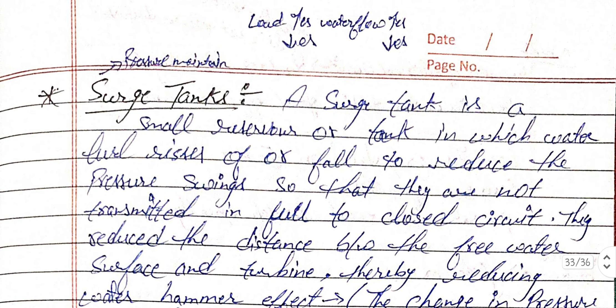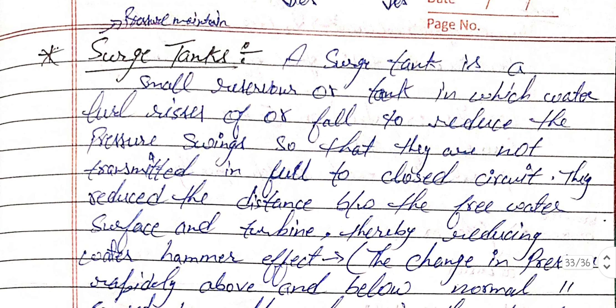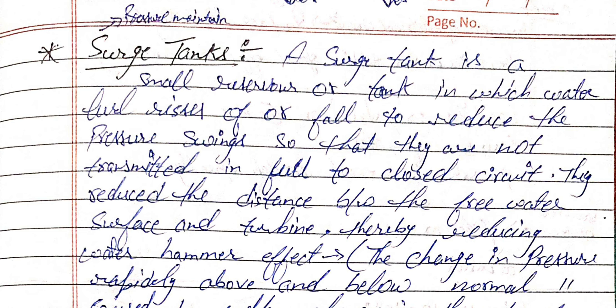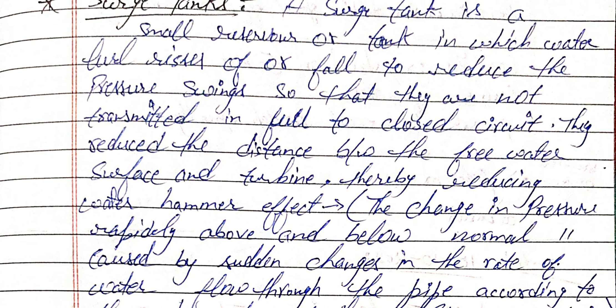The next point is the surge tank. The main purpose of the surge tank is to maintain pressure. A surge tank is a small reservoir or tank in which the water level rises or falls to reduce pressure swings so that they cannot be transmitted in full to the closed circuit. It reduces the distance between the free water surface and the turbine, thereby reducing the water hammer effect.